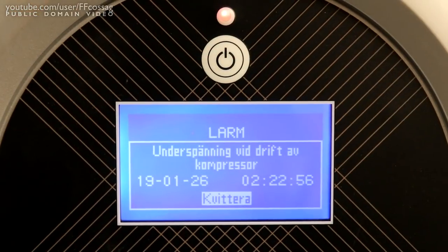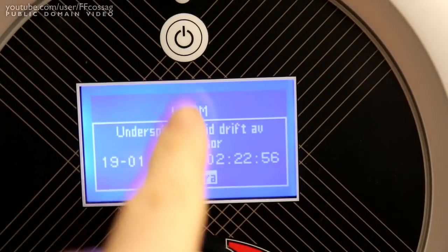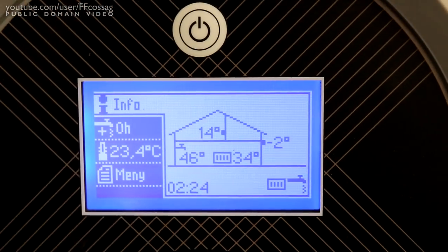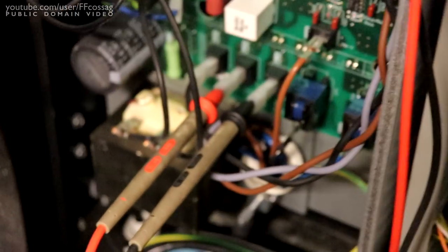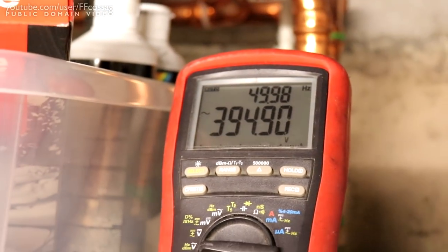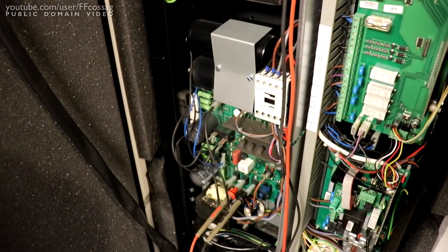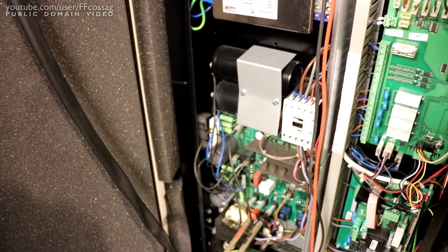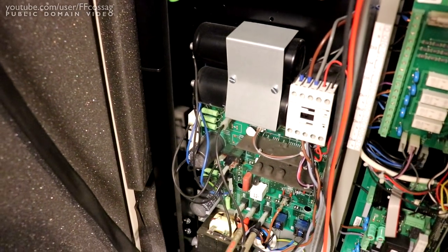I think we're going to pursue the power resistor since it's obviously involved with these caps and these caps are dead, could be a shorted cap as well but we'll see. Ah there we go, that's what I wake up to at 5:40 a.m. this morning. I don't know how to get this thing to speak anything other than Swedish but it's not running and I am just verifying that we actually have power going into the big VFD and that seems to be the case so that's the incoming three phase mains there with two probes shoved in and we have phases going in. So power going into the VFD drive board but no power in the mains rectifier caps and an open circuit big resistor that's associated with the big caps, I think that's a quite definite diagnosis.